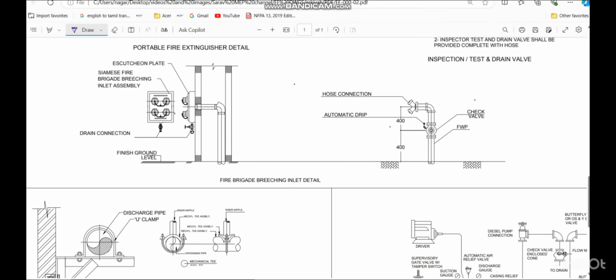And coming to the breaching inlet, which we also call the fire department connection. In our project, with the same arrangement, we have the fire department connection on the ground floor. From the ground floor, it goes down to the first basement, where we have the fire pump room. In the breaching inlet connection, we must have one drain connection as indicated here. After that, this connection must have one check valve or non-return valve, and providing an isolation valve, gate valve or butterfly valve is not allowed as per NFPA 13 in the breaching inlet connection.